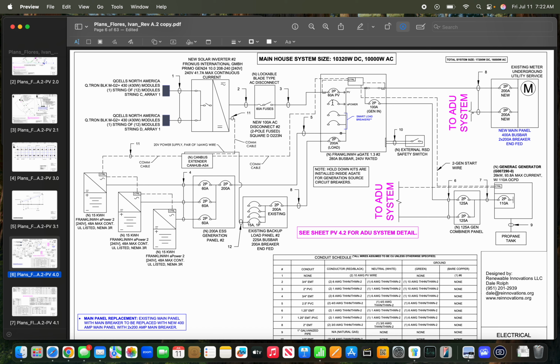This is the automatic transfer switch. This is what everything connects to: the generator, the solar, and the Franklin aPower2 batteries. Without this, you couldn't do backup in this type of configuration. Even with Tesla Powerwalls, which sadly don't support generators, you'd need this if trying to use a generator, because their backup switch isn't compatible with 400 amps.